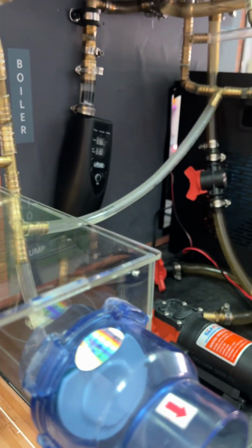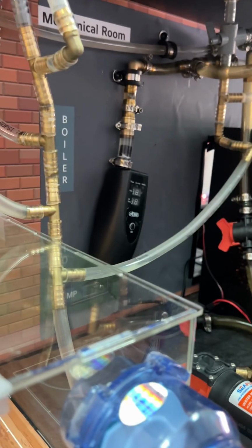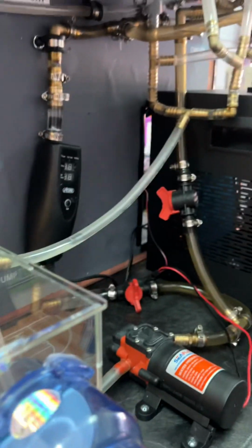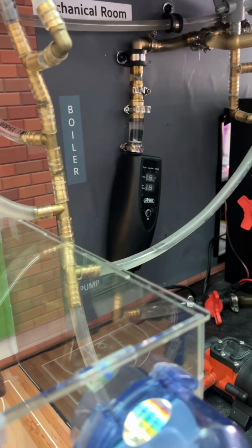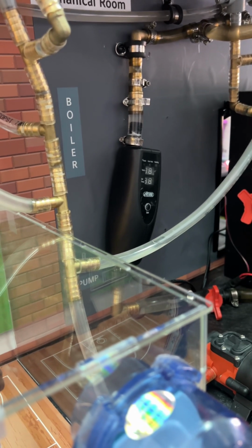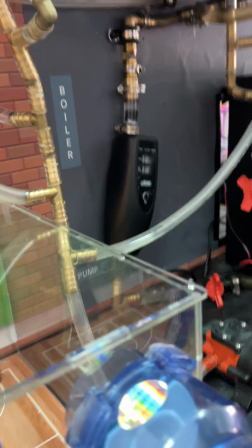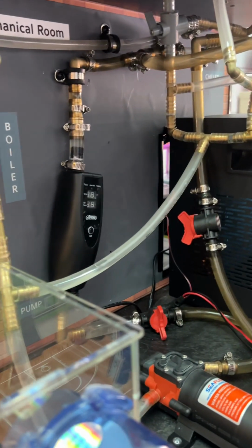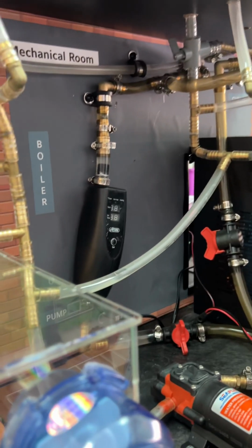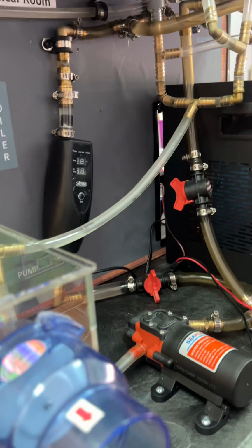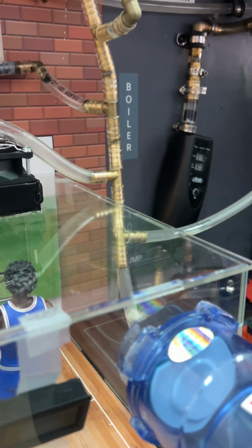A real unit has a condensate pan under it. The condensation off those coils, as it takes the humidity out of the air and the coils reach dew point, drips off into a pan, like in our refrigerator, goes into a drain, and the drain takes it away. So all units in the real building have condensate pans that take the condensate water away in the summer when you're running air conditioning there. Like a dripping window air conditioner unit? Right, exactly, like a dripping window unit, which a lot of people are familiar with.